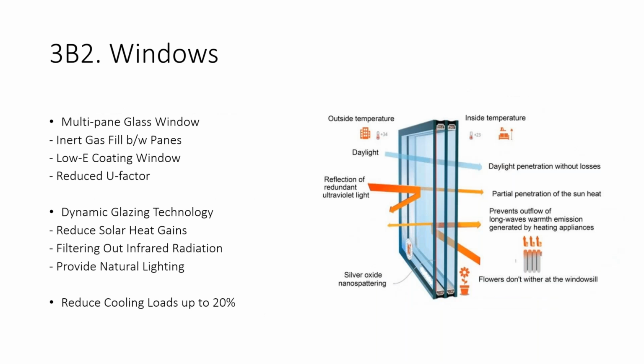The second main component of a building is the windows, and we have technology available that we can get multi-pane glass windows with inert gas fill, which gives us the insulation and reduces the U factor of the window. The technology we have right now also includes dynamic glazing, which reduces solar heat gains by filtering out infrared radiation and lets the natural light pass through the window. It's really helpful, and just using those windows, we can increase our air conditioning efficiency by 20%, or we can decrease our cooling loads by 20%, vice versa.